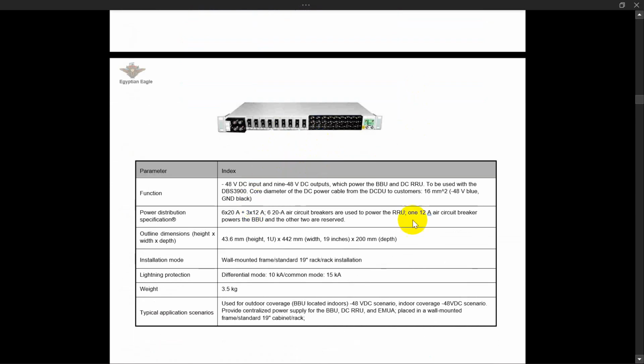The same applies to the DCDU. The DCDU needs to be fixed inside the 19-inch rack, and here is the specification: 3.5 kg. It comes from the rectifier with a minus 48 input, and from it we can get 9 minus 48 outputs. So we are distributing the DC power we get from the rectifier through our DCDU. This is one important point. For the DCDU, the power cable should be in the 16 mm range because it has to hold 9 outputs. So to keep the cable secure and cover the load, we use a big cable between the DCDU and the rectifier.